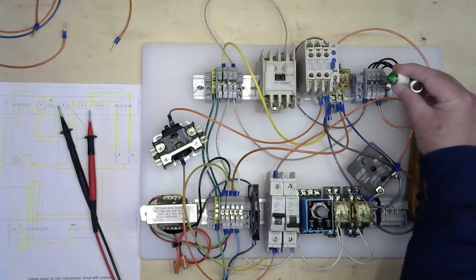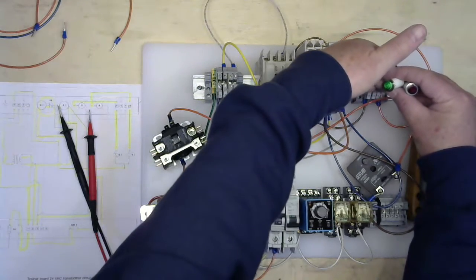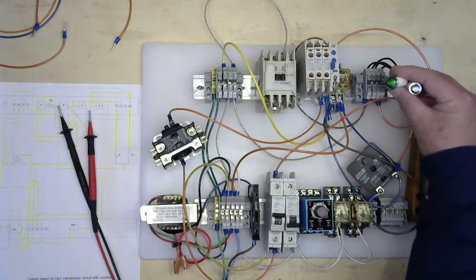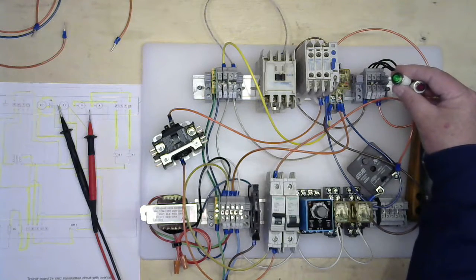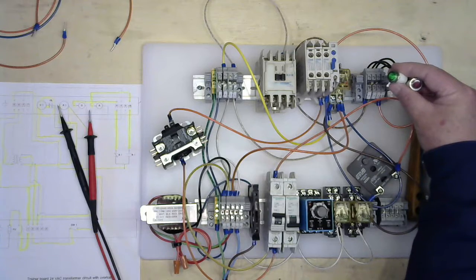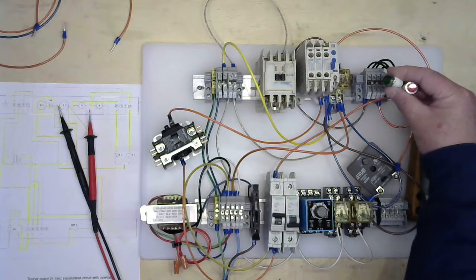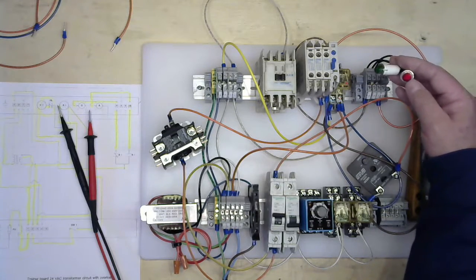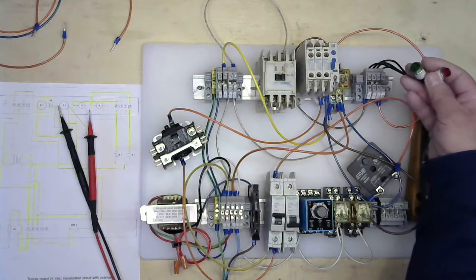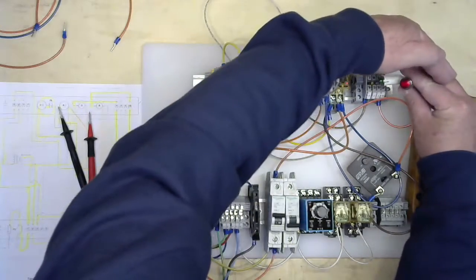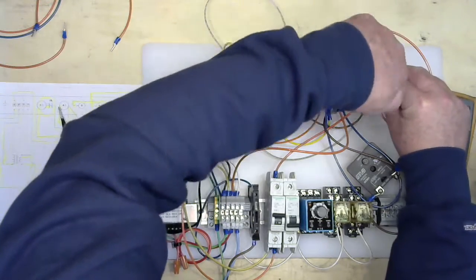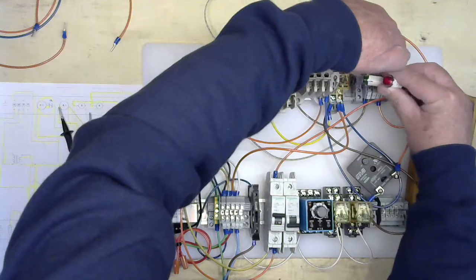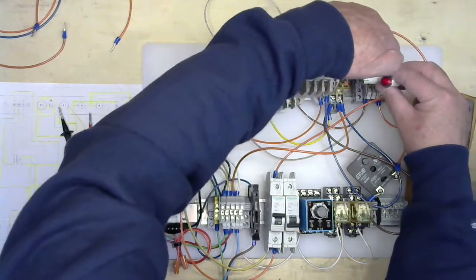Still showing a green indicator light versus a red. And right now we want to wait for the time delay on make, the time delay, to finish timing out, to close the relay contacts for our set here. We just had a change. My relay came on and my red light indicator here came on. A little harder to see it, and the lights we have, you can kind of get a general idea. The green went off and red came on.